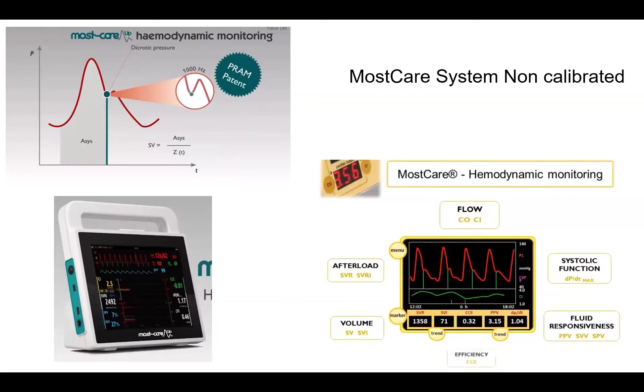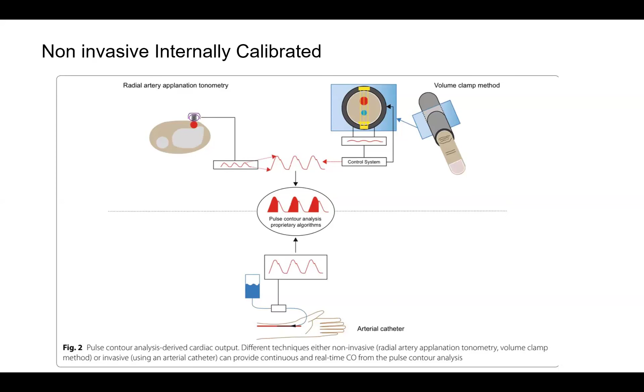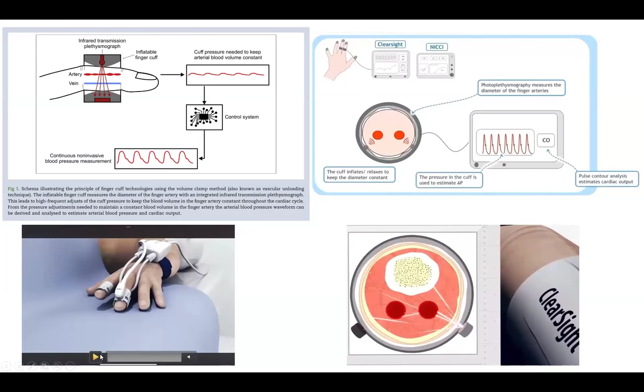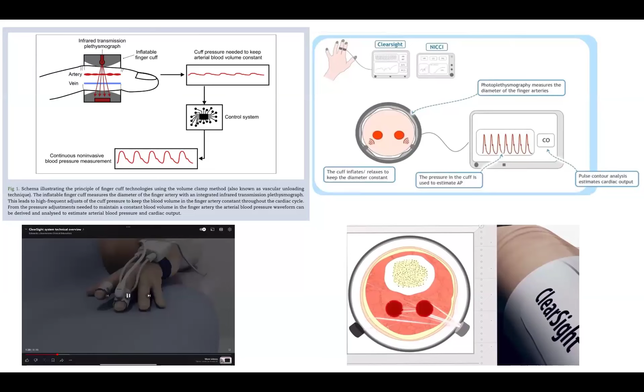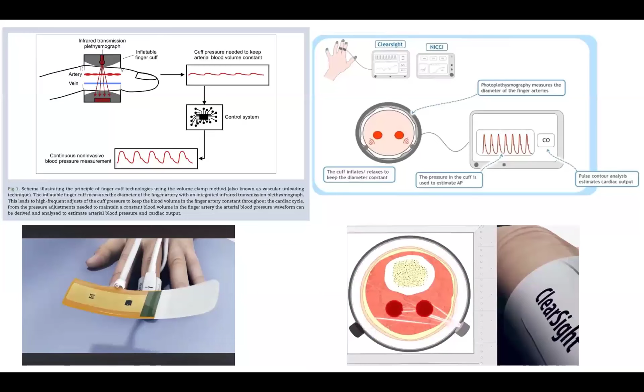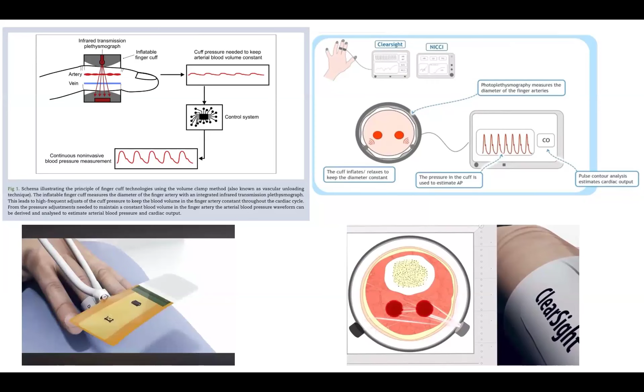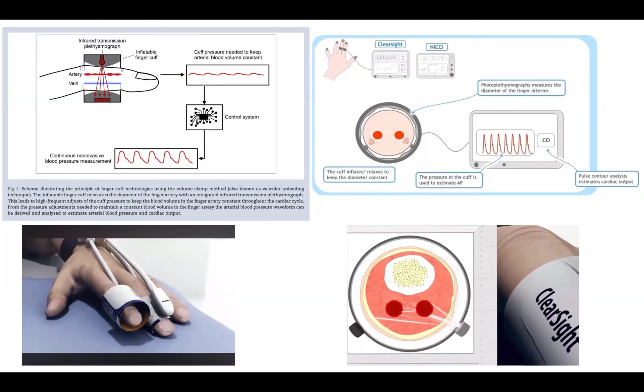So there are several methods for non-invasive pulse wave analysis, for example, the volume clamp method and the radial artery applanation tonometry. Here we're going to discuss the ClearSight system, which uses a volume clamp method. The sensor contains an inflatable finger cuff and an infrared plethysmograph that measures blood volume in the finger arteries, which is changing during the cardiac cycle as a result of changes in the arterial pressure. An automated feedback system inflates and deflates the finger cuff rapidly in order to keep the volume of the finger arteries constant by applying a counter pressure. From this counter pressure, the AP waveform is reconstructed indirectly and is analyzed by pulse wave analysis to give the cardiac output.